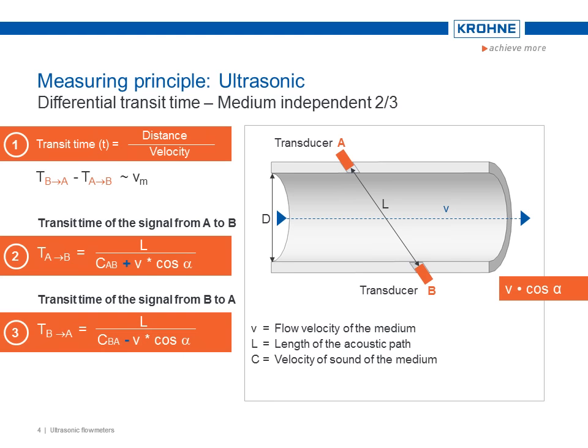The transit time of the signal is measured and then used with other variables to calculate the flow. Although the signal travels in a straight line, it is traveling at an angle, alpha, to the pipe axis.